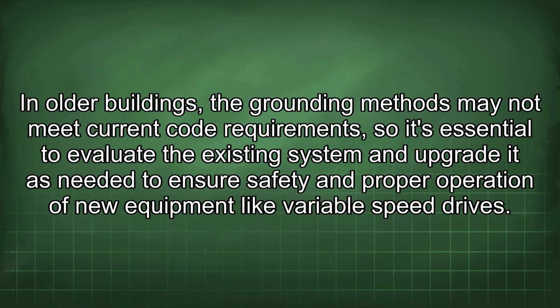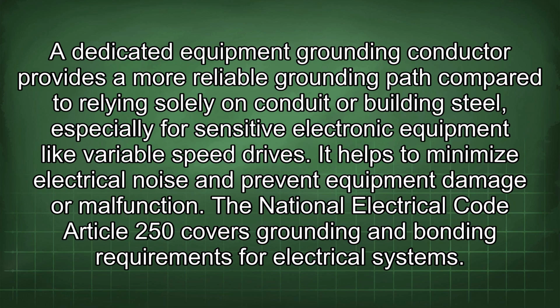In older buildings, the grounding methods may not meet current code requirements, so it's essential to evaluate the existing system and upgrade it as needed to ensure safety and proper operation of new equipment like variable speed drives. A dedicated equipment grounding conductor provides a more reliable grounding path compared to relying solely on conduits or building steel, especially for sensitive electronic equipment like variable speed drives. It helps to minimize electrical noise and prevent equipment damage or malfunction.